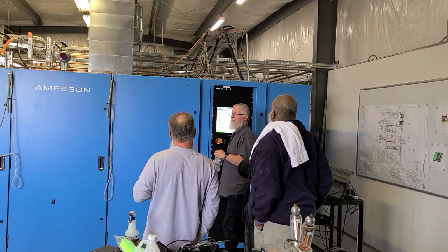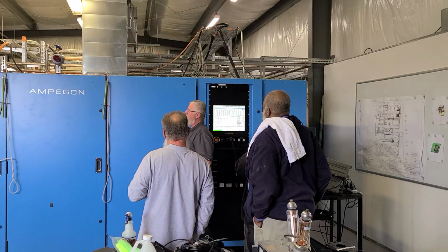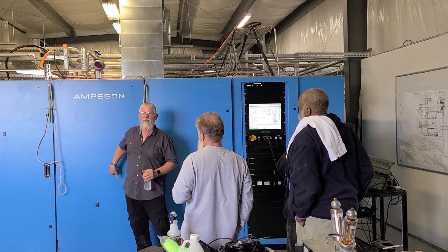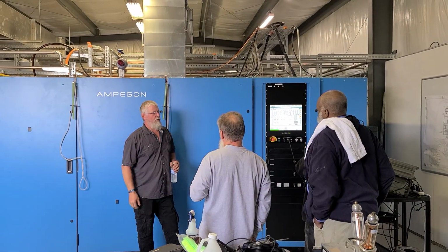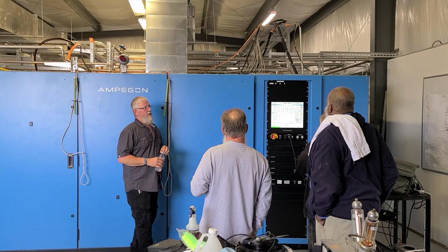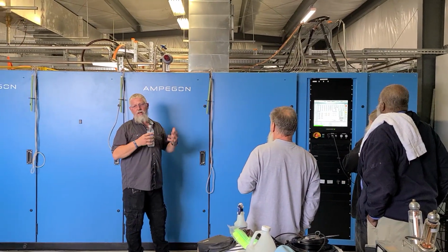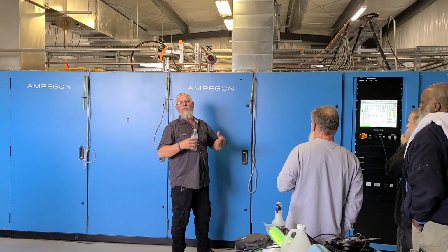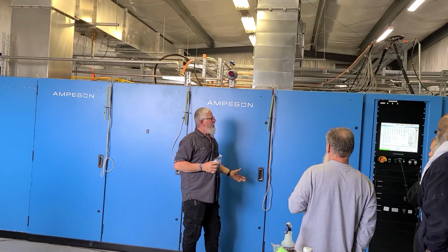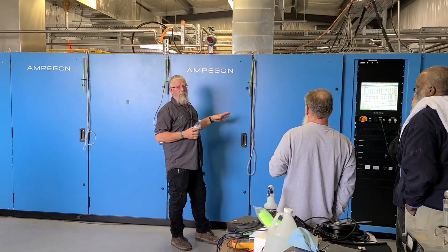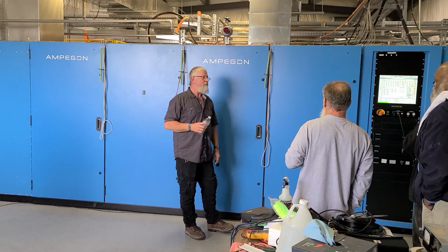This is a 2-minute process, and the big thing it's doing now is taking that up to 300 degrees - it's called red heat. That's where, instead of heating it with the RF which would be instant, that's how the old one was - they actually bring the temperature up gradually, which preserves the life of that tube.